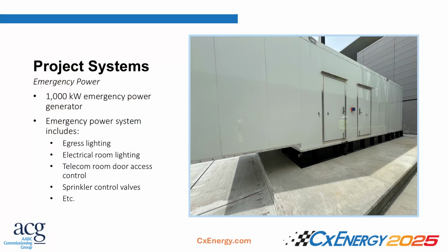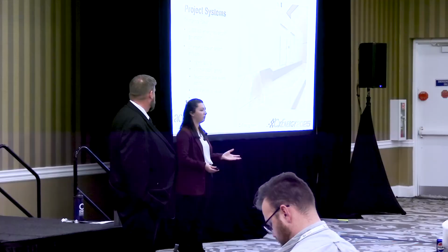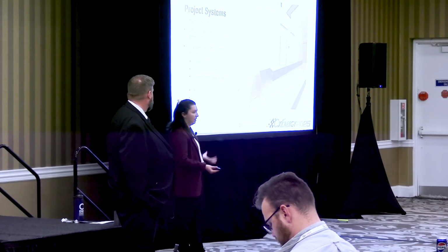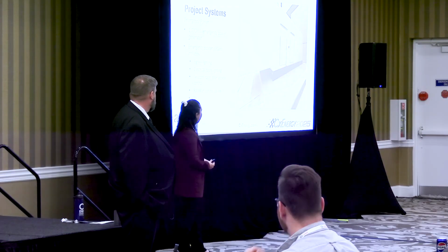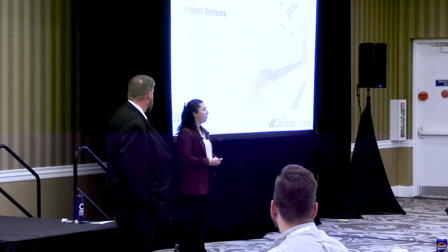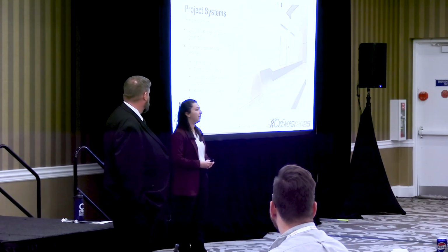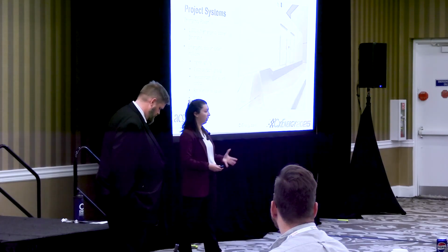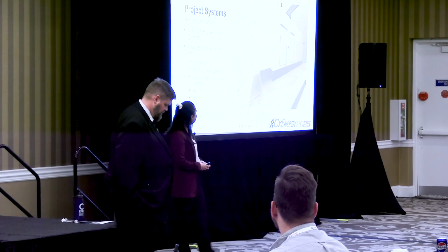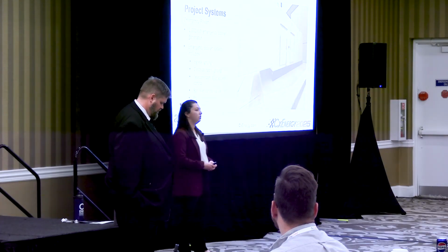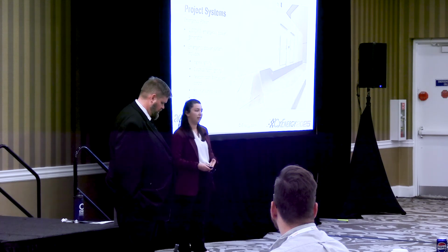Next up, we had the emergency power system. They had a 1,000 kilowatt emergency power generator for the project, serving the emergency lighting, telecom rooms, fire sprinklers, anything you would need active still in an emergency. So they had a 24-hour load test, a 24-hour burn-in to test this generator, and we were intended to be there to witness the testing.